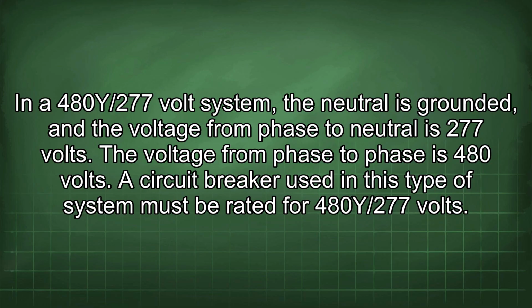In a 480/277 volt system, the neutral is grounded, and the voltage from phase to neutral is 277 volts. The voltage from phase to phase is 480 volts. A circuit breaker used in this type of system must be rated for 480/277 volts.